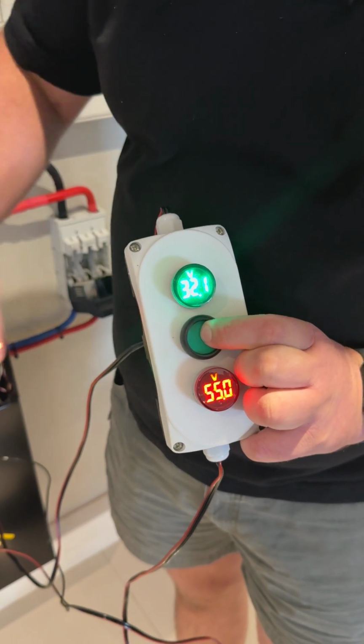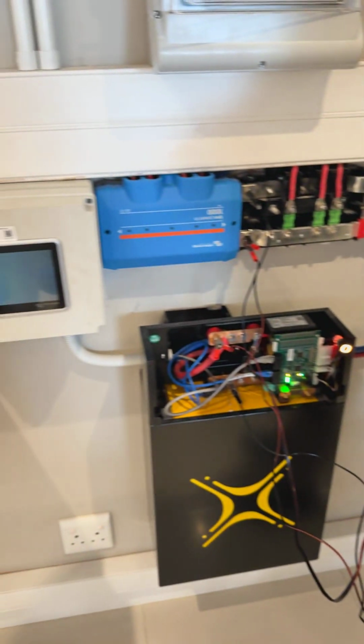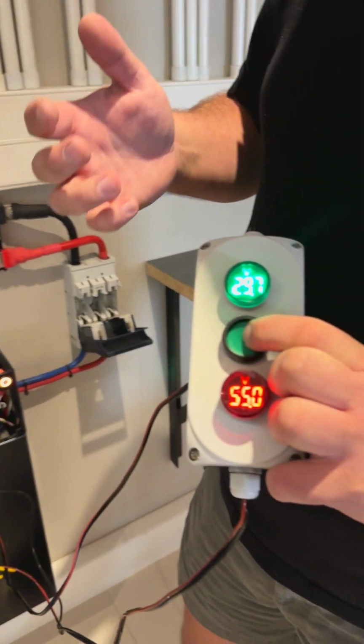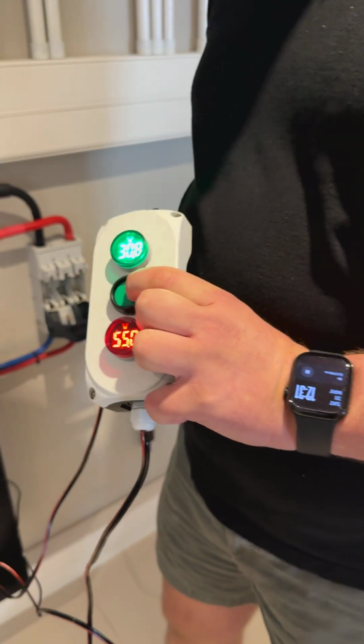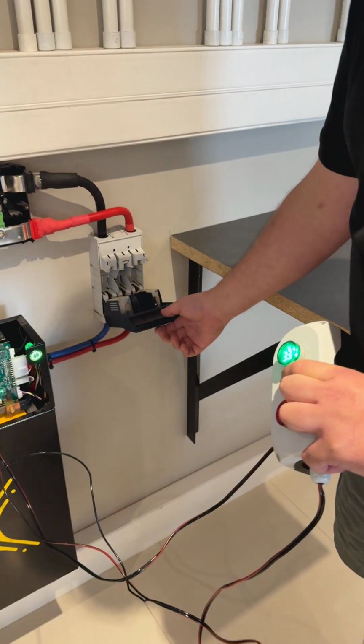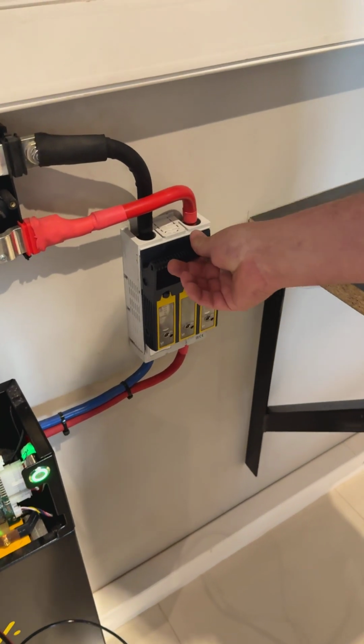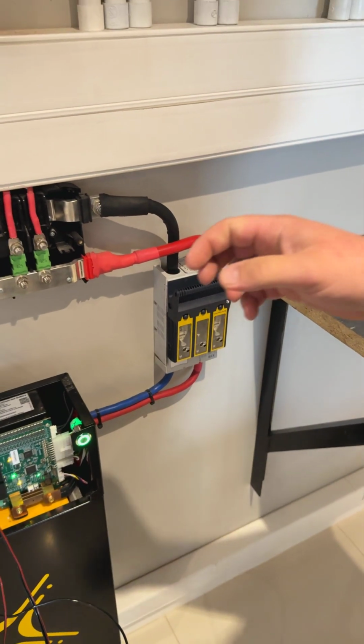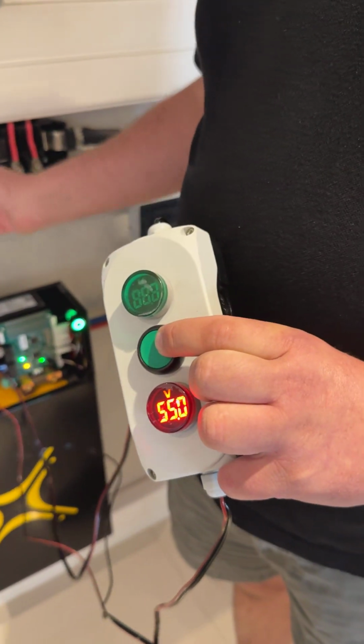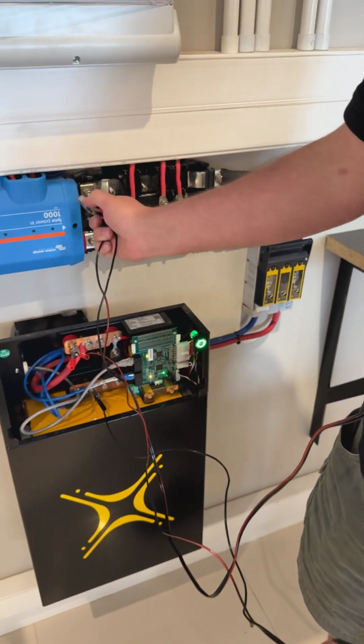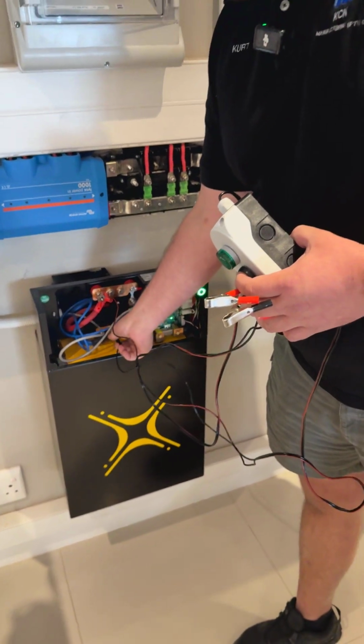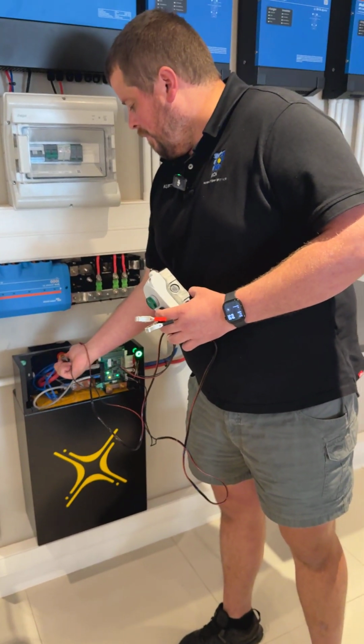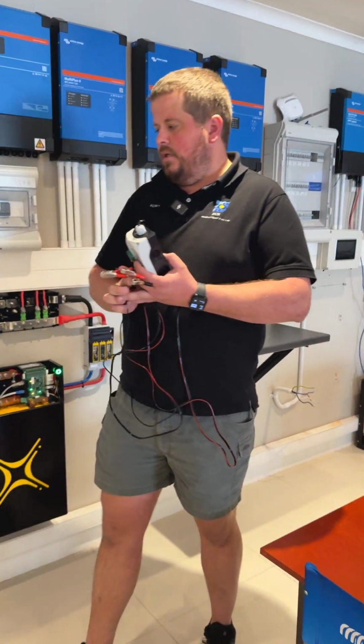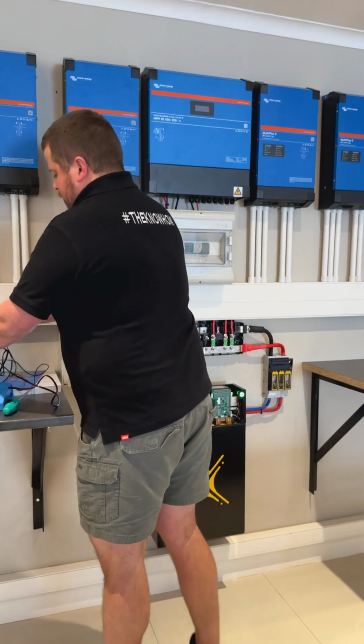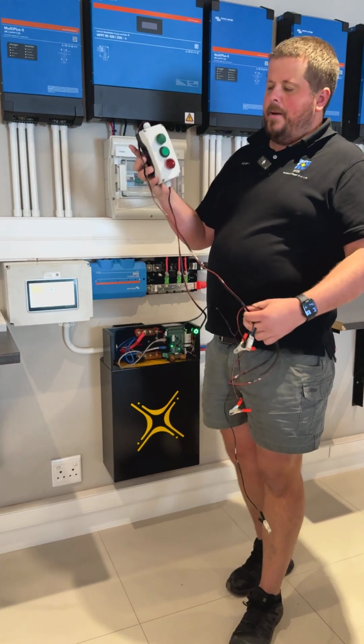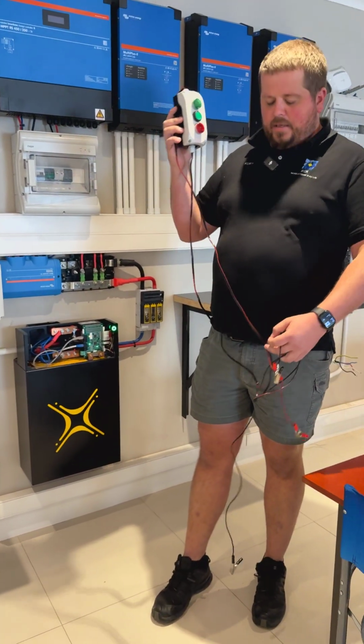Now the color control is pulling power, everything is pulling power. So I always say to guys, as soon as the voltage goes up and through, if I close this, there's no arc from that on the battery terminals. You disconnect it, and there's no problems.